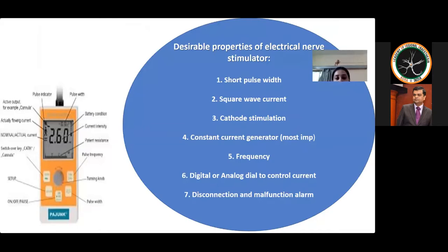Then there should be a square wave current, that is the abrupt rise and fall, as a slow rising current will cause accommodation. So the abrupt rise and fall, that is a square wave current, is more beneficial than the slow rising current. Then there should be a preferential cathode stimulation, that is, the cathode should be used as the stimulating electrode which is connected to the needle to depolarize the nerve rather than an anode. Then a constant current generator is used, not a fixed one, which is one of the most important features of the peripheral nerve stimulator, as a constant current has to be produced with the changing impedances. Then we have frequency. 2 hertz is used, better than 1 hertz, because the manipulation of the needle is much better.